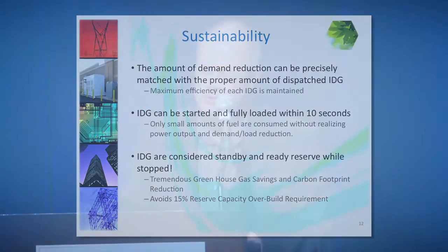Incident took place in southern Florida. They lost about 3,000 megawatts. There was an incident on transmission and it tripped out generation. We were able to dispatch 200 megawatts in about 20 seconds into South Florida to help the grid stay together. That's how fast you can start this stuff. Hospitals have a requirement, 10 seconds. Otherwise, people aren't hanging around too long. You have to get this up.